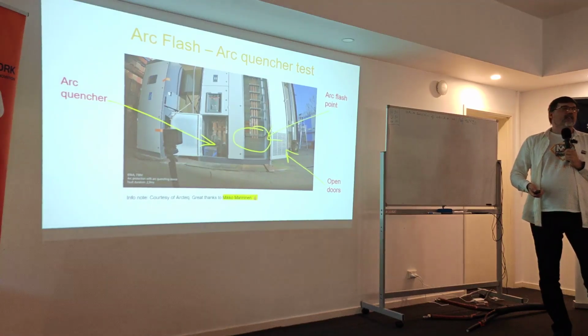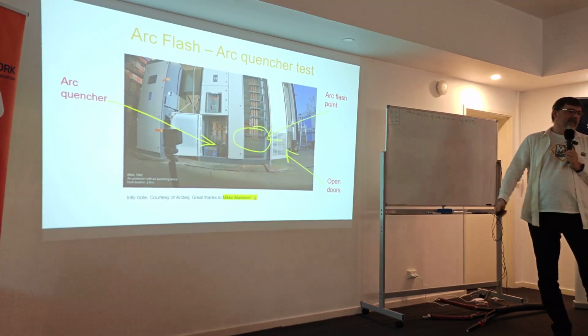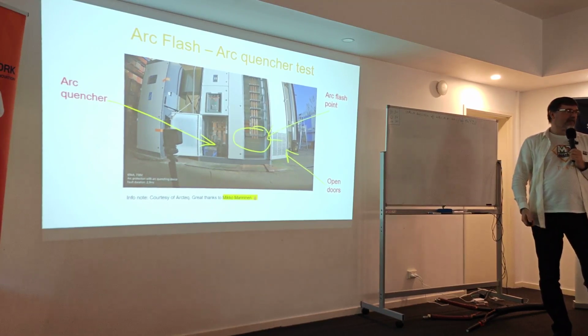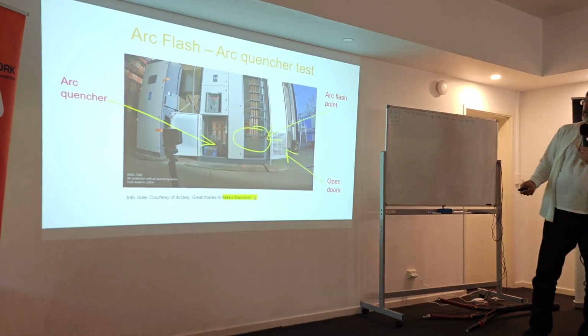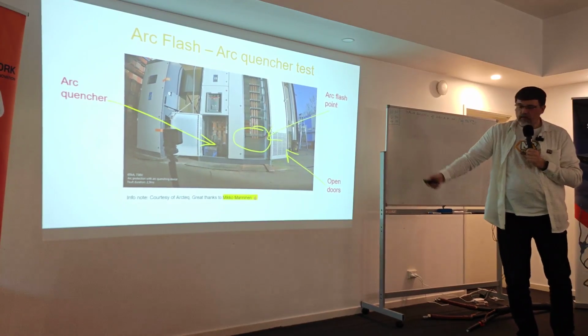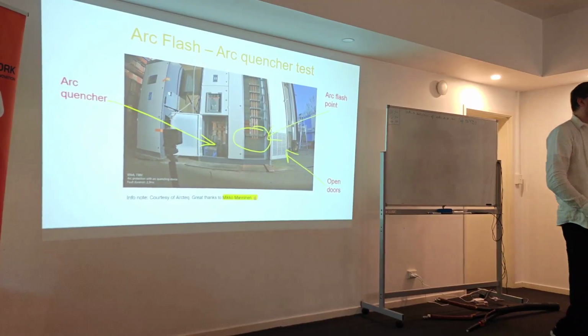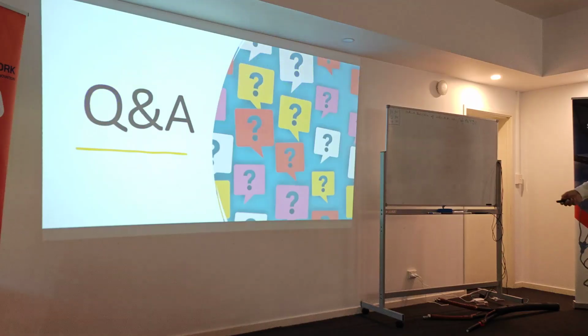That's not how a 65 kiloamp arc looks. The only weird thing is that I told them they should do the damage test after it and show the difference between with and without. They didn't destroy the switchgear. But nevertheless, this is the fastest thing, and most of the time the most expensive. And I went very fast because I want to go to the calculation part. So if you have a question, feel free to ask.